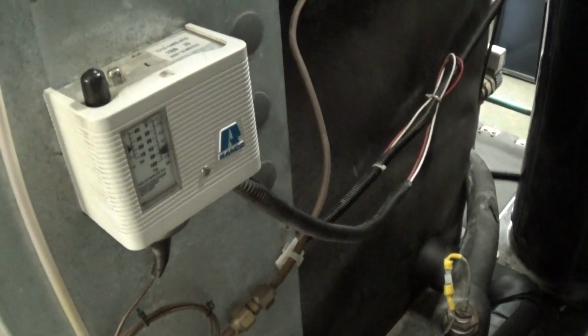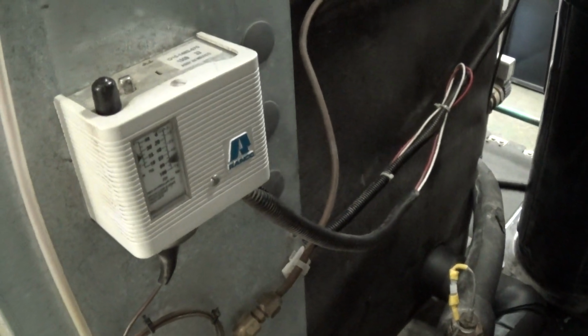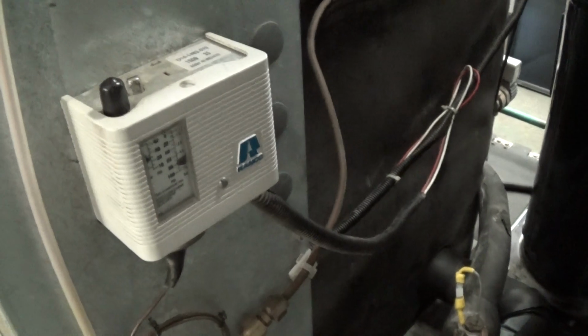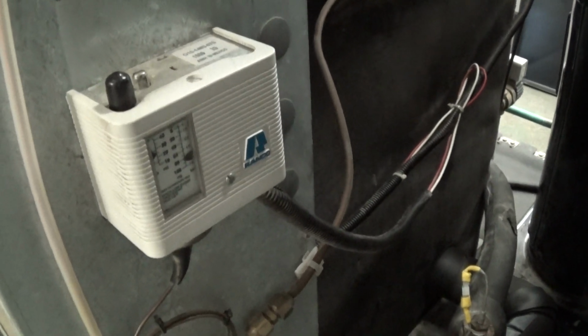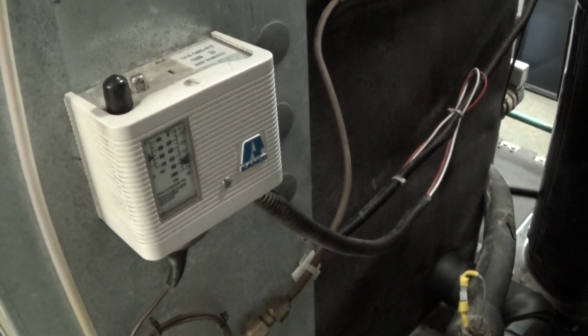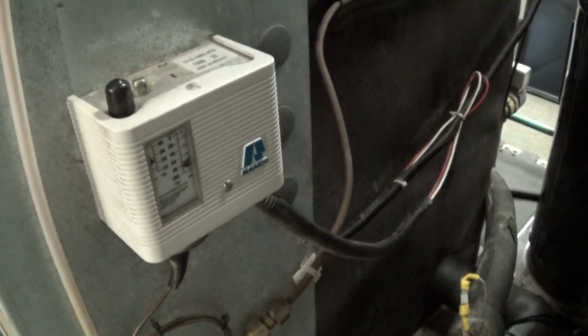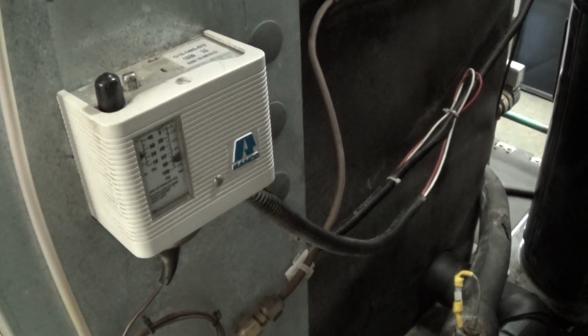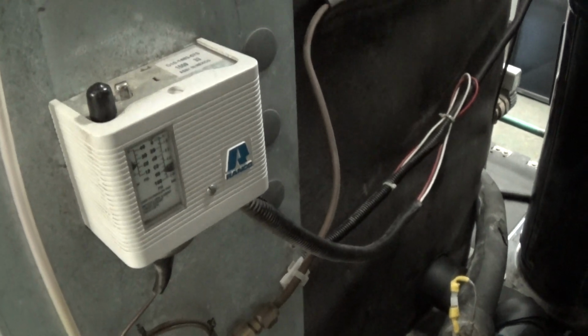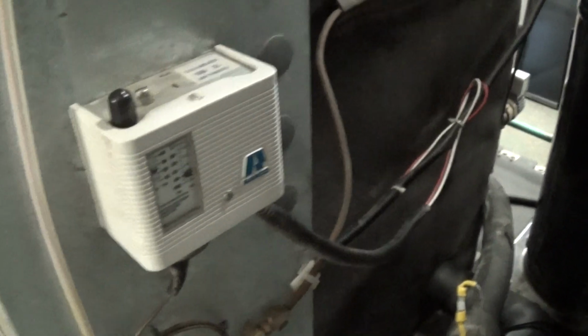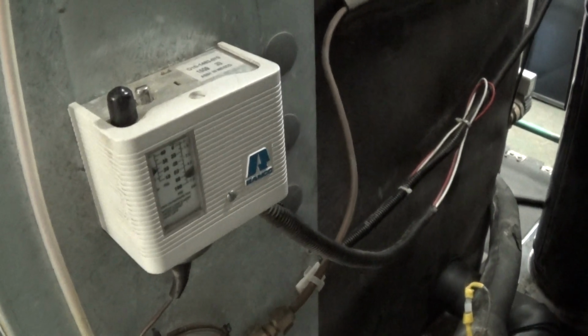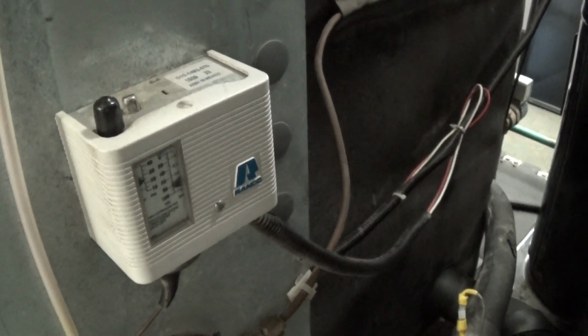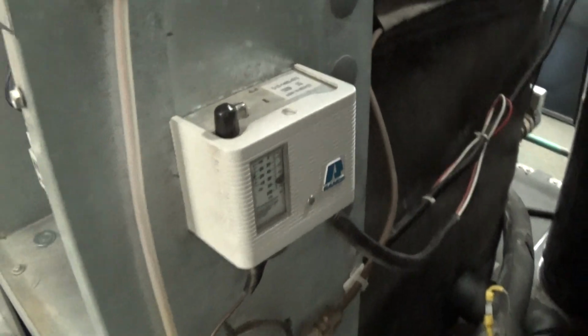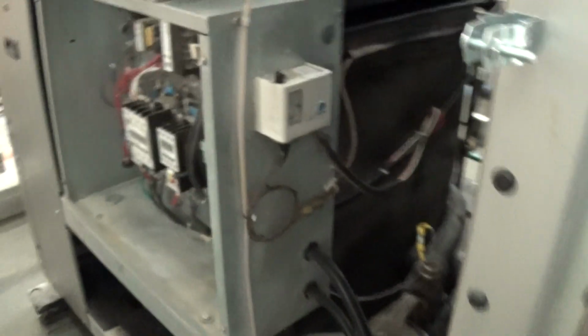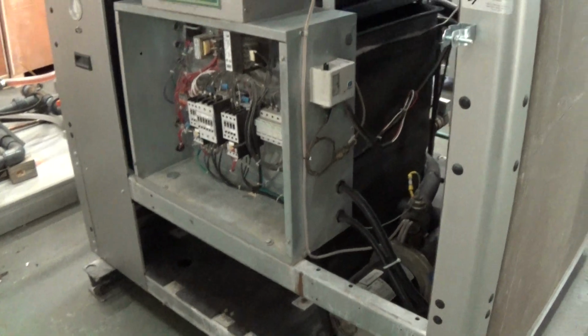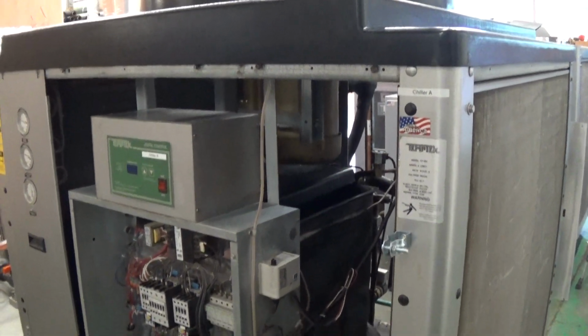Low pressure will happen if you're actually low on refrigerant, or low pressure may be tripped also if you have some flow problems and getting too little flow through the heat exchanger. Then it gets colder inside the heat exchanger, and we may trip out on the low pressure safety switch. Both the low pressure and the high pressure are there to protect the refrigerant compressor, of course. We'll come back to video number 2 in a second.